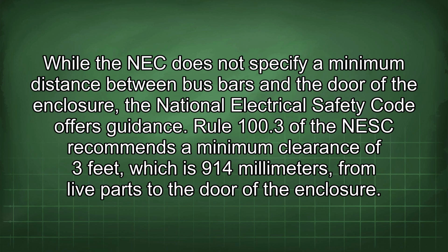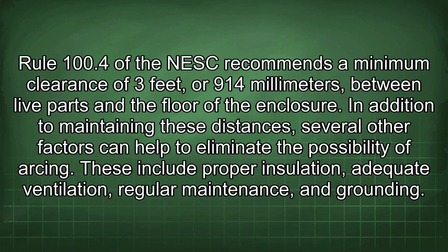Rule 100.3 of the NESC recommends a minimum clearance of 3 feet, which is 914 millimeters, from live parts to the door of the enclosure. Rule 100.4 of the NESC recommends a minimum clearance of 3 feet, or 914 millimeters, between live parts and the floor of the enclosure. In addition to maintaining these distances, several other factors can help to eliminate the possibility of arcing. These include proper insulation, adequate ventilation, regular maintenance, and grounding.